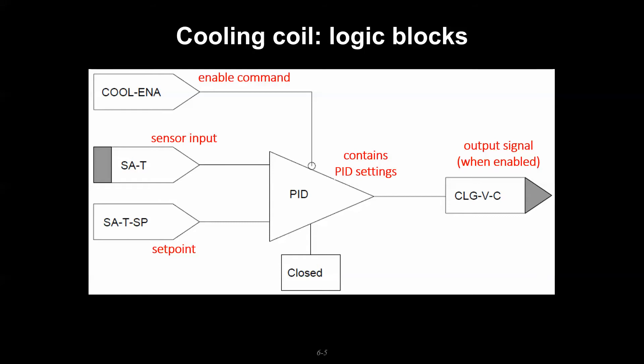Here we have some enable command because we may not want that PID loop to operate at all times. When we're not operating that PID loop, say when we're unoccupied, we're going to tell the valve command what we want it to be - say closed.